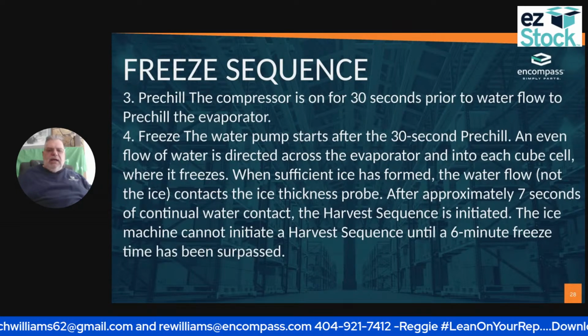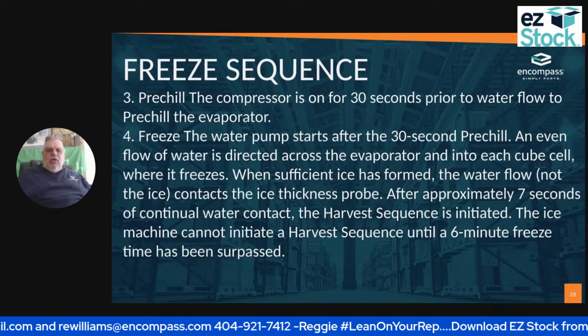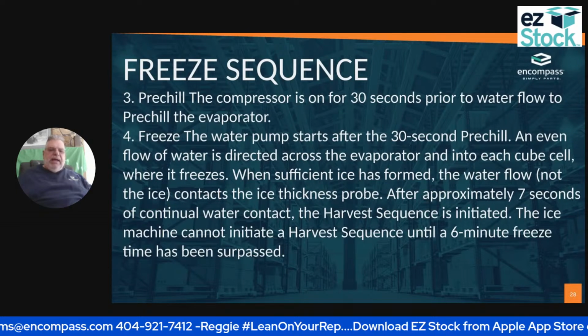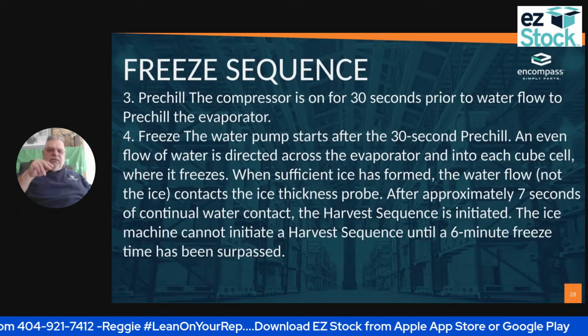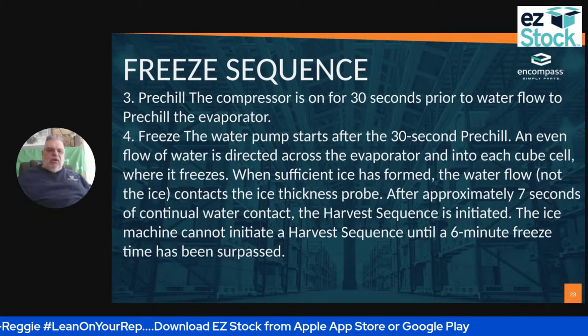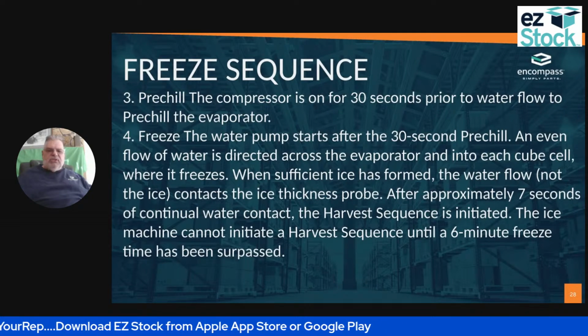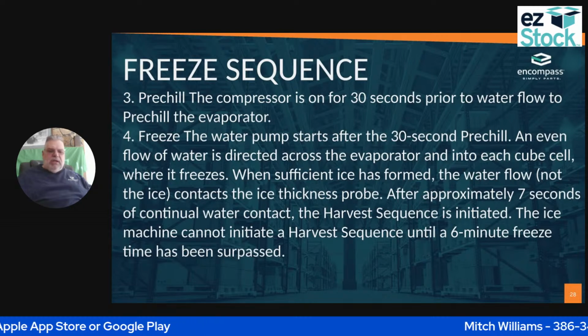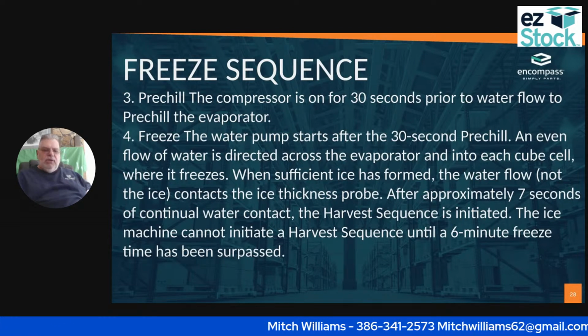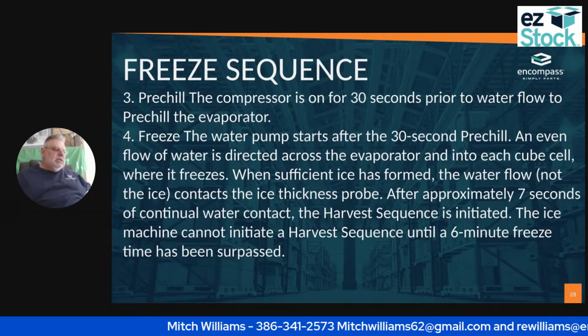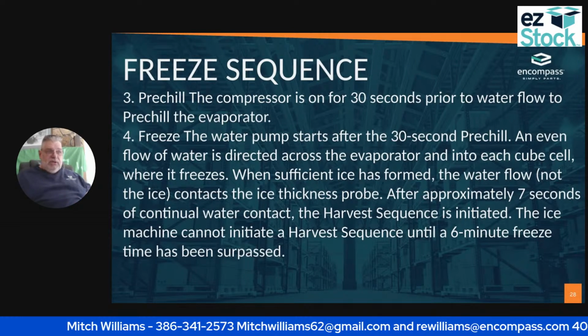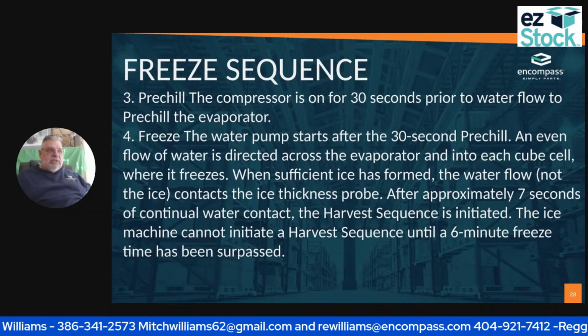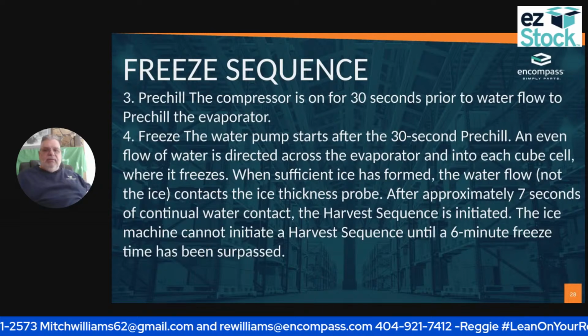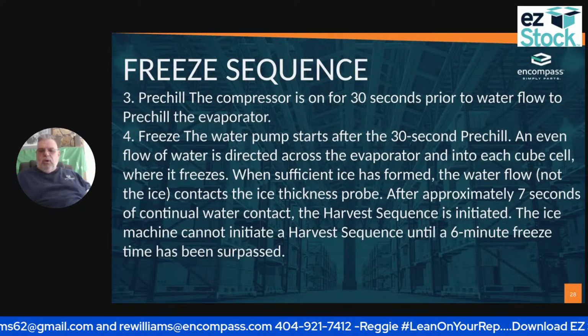When sufficient ice has formed, the water flow contacts the ice thickness probe, raises it up, and starts a 7 second harvest. The ice machine cannot initiate a harvest cycle until a 6-minute freeze time has passed. If it freezes before the 6 minutes has passed, it doesn't work properly.